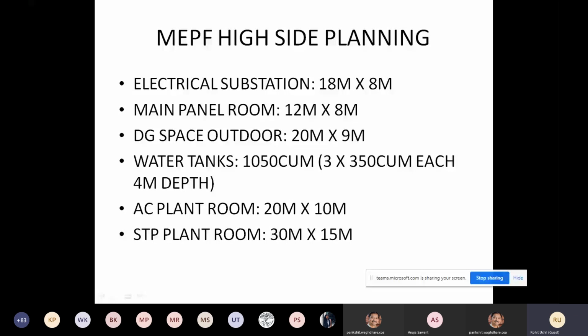If you require to provide DG backup, then you need an outdoor space, because DGs are preferably placed outside. They become hot and they require a lot of ventilation if they are placed in basements. Then you require the space or the footprint for the water tanks, and then also for your AC plant room and STP plant room, that's about 20 meters by 10 meters and 30 meters by 15 meters. These are approximate sizes for a building of maybe 300 to 400,000 square feet of built-up area.